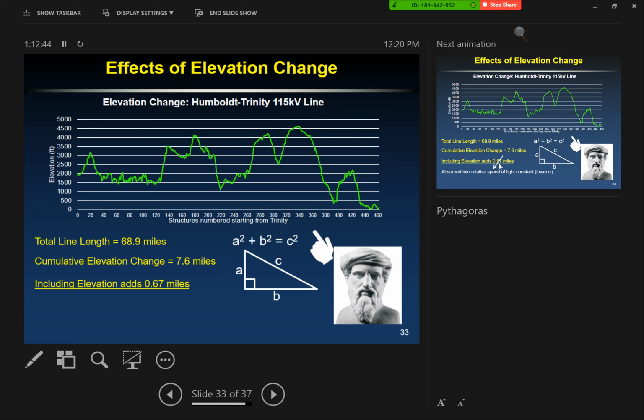The thing is, when you test your line over this 0.67 miles, you're going to test the propagation along that line and you'll just get a lower speed of light constant factor. So instead of 0.98, the effect of this might make it look like 0.976 or something—it just gets absorbed into your relative speed of light factor. That's assuming it's relatively constant over the whole length of the line.